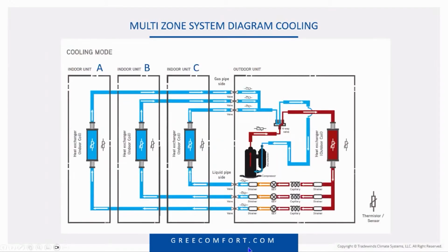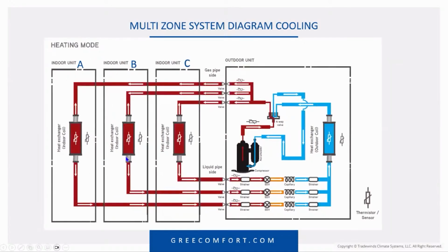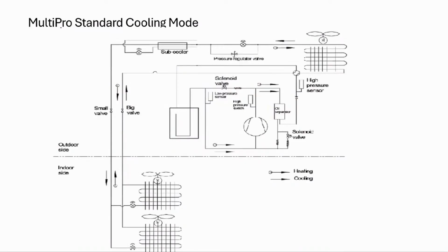So we go into a multi-zone. You've got a set of refrigerant lines for each indoor unit. So one indoor unit is going to have a gas pipe, and it's also going to have a liquid pipe for each indoor coil. So when we get into MultiPRO, we're not doing that. It's a little bit different in that we are using one set of pipes out to the condenser, and to me, it's a cleaner look than a multi-zone type of system. You have one gas pipe, one liquid pipe that comes from the outdoor machine all the way to your indoor units.